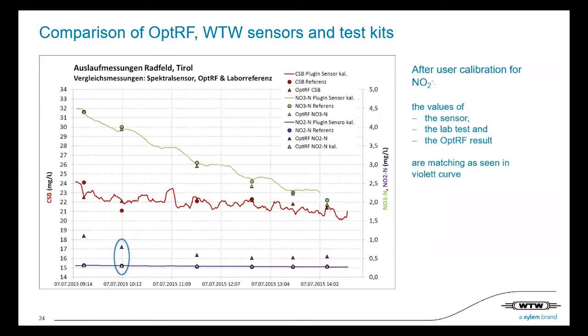We have more curves. Also in the first curve we see at the beginning, we have matching values. That's a very good result, because it also shows that if you have a good reference for all - the sensors as well as the optical reagent-free - with good routine analysis in your lab, you can also check and adjust optical sensors from the IQ sensor net.